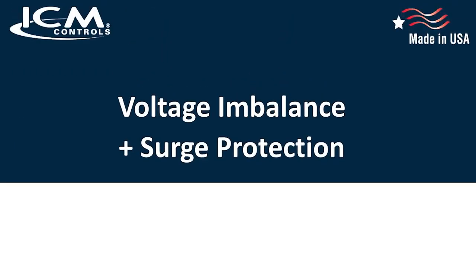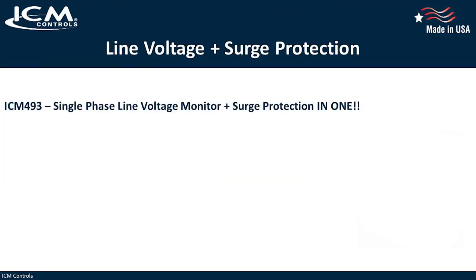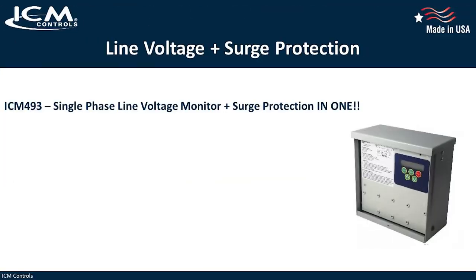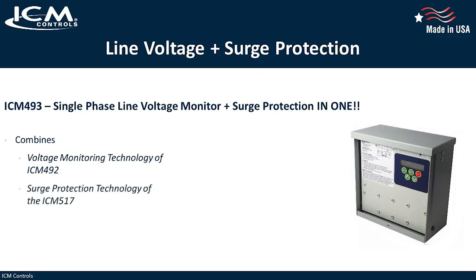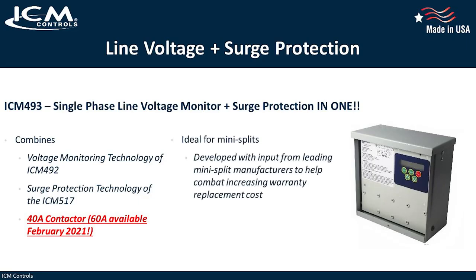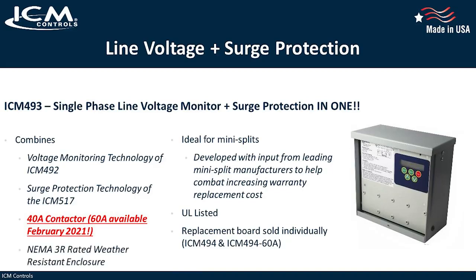The ICM 493 is a single-phase line voltage monitor that offers built-in surge protection. It combines all the bells and whistles of the ICM 492 single-phase digital line voltage monitor with the addition of a bank of TMOVs for high-quality surge protection. Plus, it has a built-in 40-amp contactor. This allows the unit to be easily wired in series with your equipment. It is UL rated as a Type 2 device and comes packaged in a NEMA 3R rated weather-resistant enclosure.